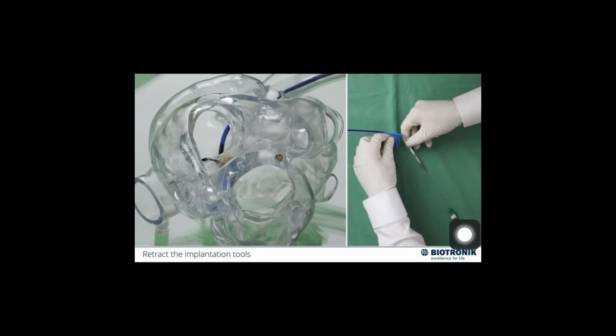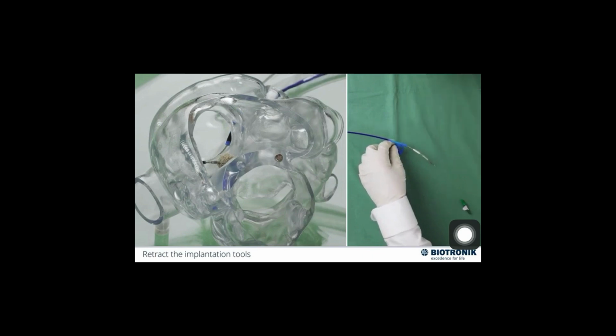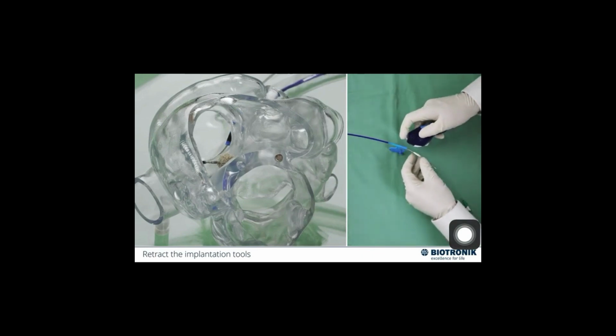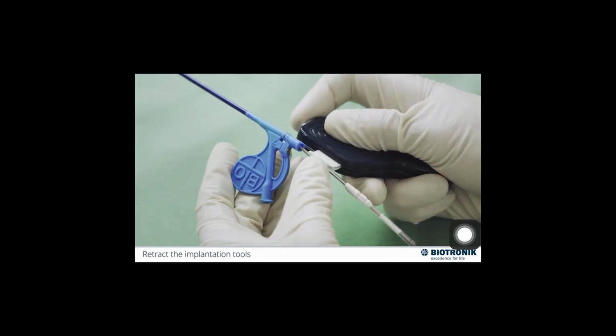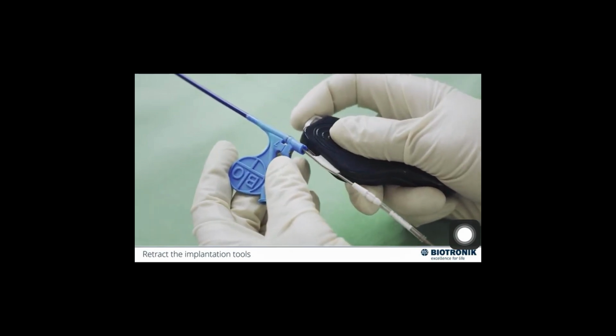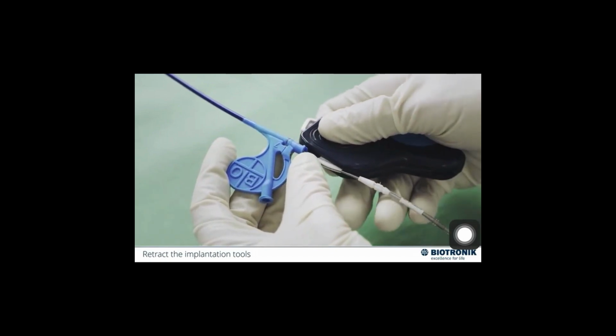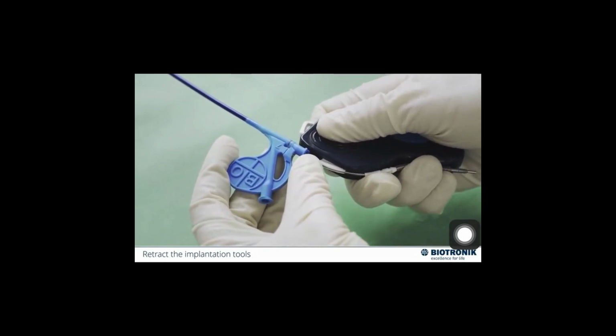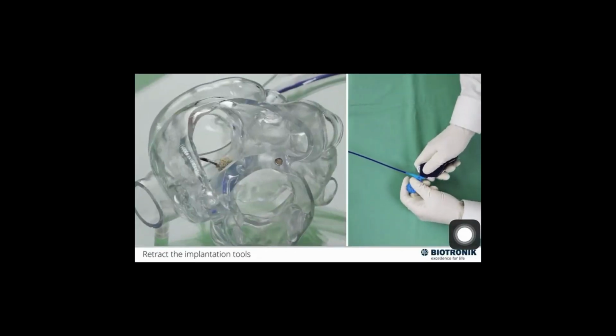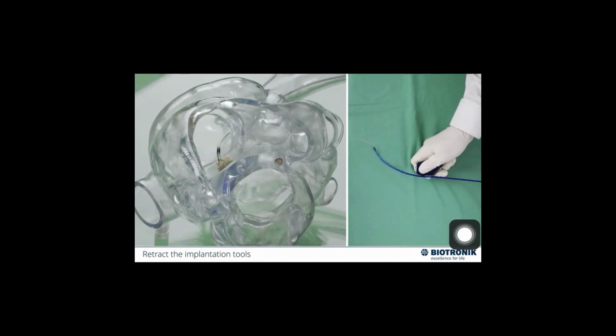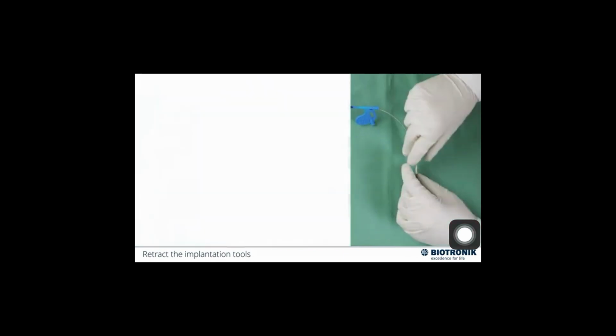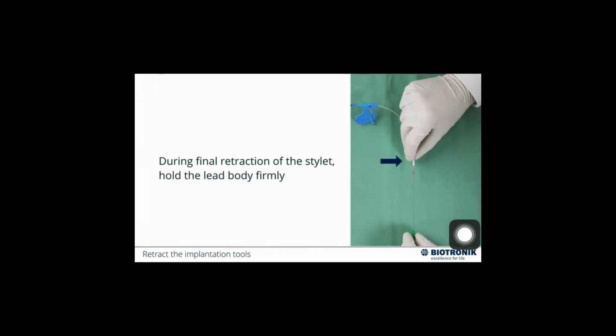Ensure there is sufficient space to fixate the slitting tool onto the lead. Load the lead into the slitter guide's white clamps. Place the blade at 180 degrees related to the catheter handle and the release button. Fit the lead into the slitter groove and hold with your finger. Keep blade parallel to the catheter during slitting and perform a single smooth pull action. During final retraction of the stylet, hold the lead body firmly.